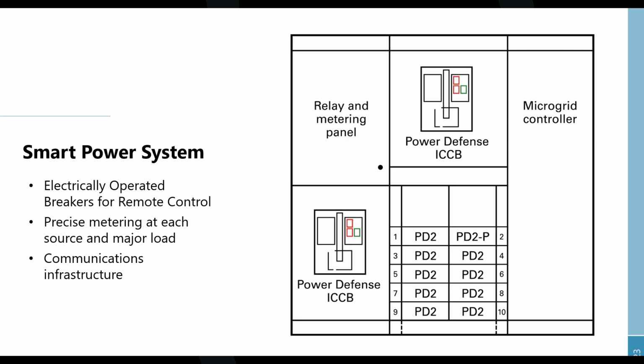These big power defense breakers, as they're called, are expensive, significantly more than a regular breaker, but each one is actually taking the place of an automatic transfer switch. So the extra tens of thousands of dollars for these advanced breakers gets offset on your project by removing the tens of thousands of dollars in space and cost of automatic transfer switches. In the end, you actually take up less space with a microgrid electrical distribution system.